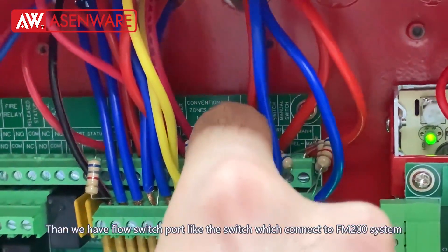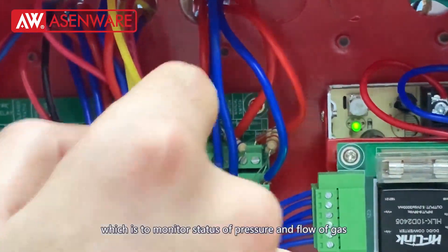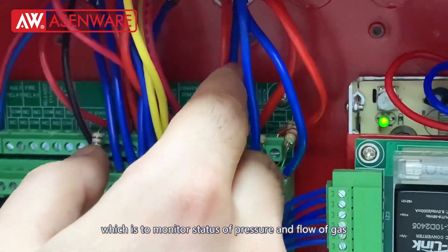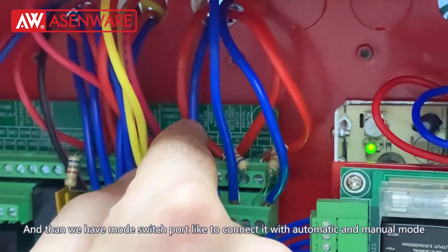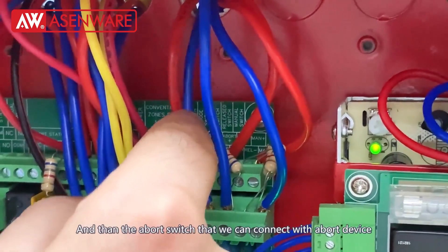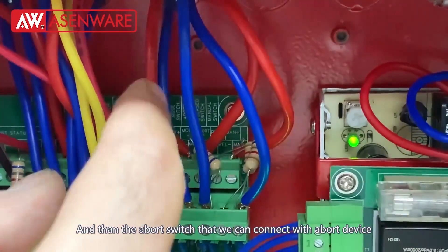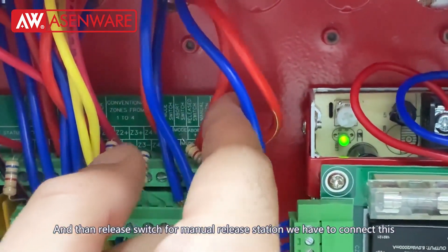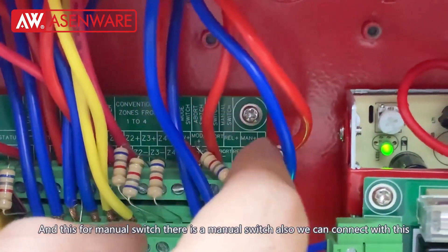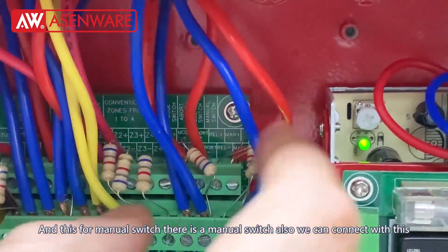Then we have a flow switch — there is a switch with the FM200 panel that needs to connect with this so that the panel can control the status of pressure and flow in the cylinder. And then we have the mode switch port to connect it with the automatic and manual mode. Then the abort switch port — we can connect it with the abort device. Then the release switch port for the manual release station. And this is for the manual switch — we can connect it with this.